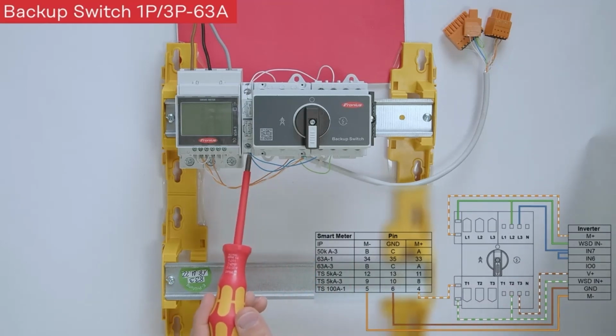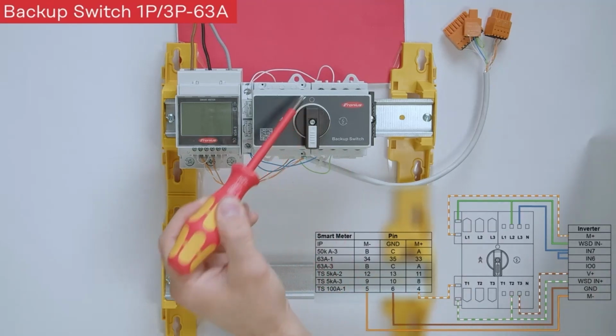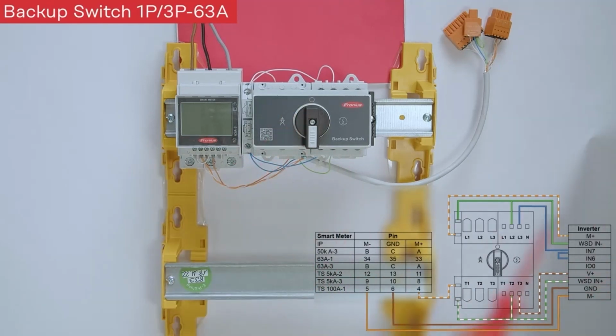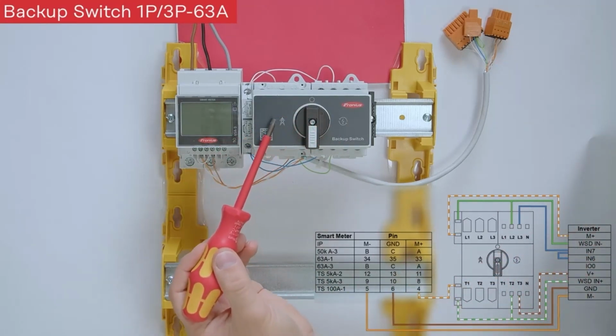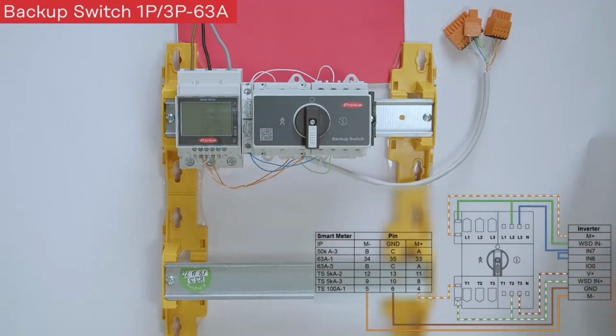First of all, we need to install the so-called WSD contact. This WSD contact now makes sure that the inverter will switch off whenever it reaches the zero position on the backup switch. So that means that the WSD contact is open in zero position, and on the other hand side it must be closed in grid parallel mode as well as in backup mode.